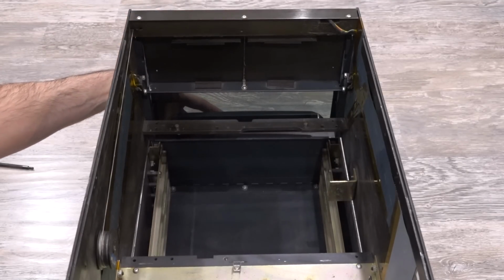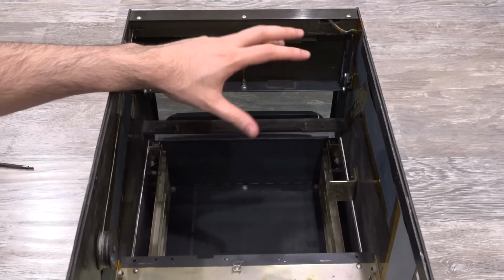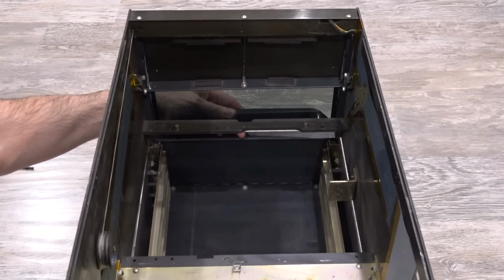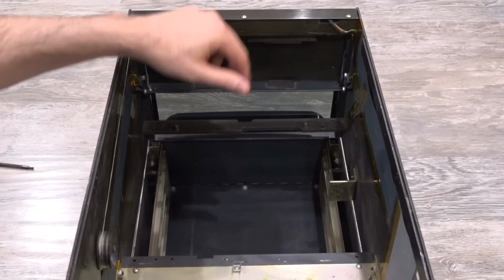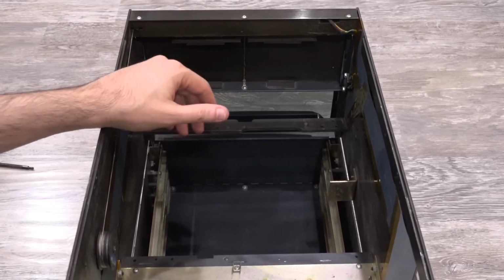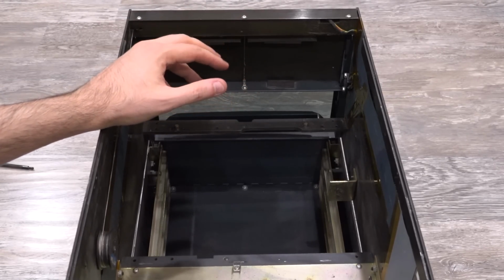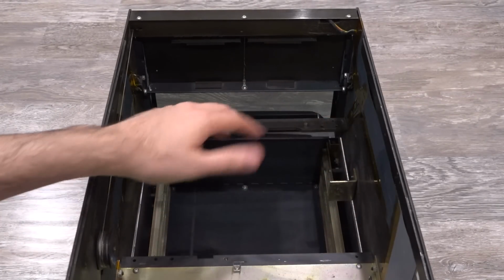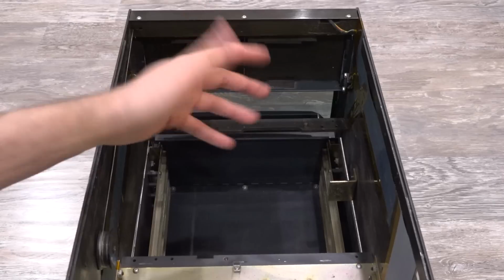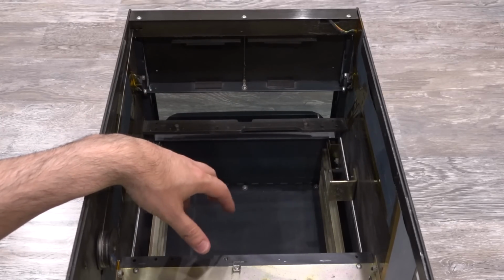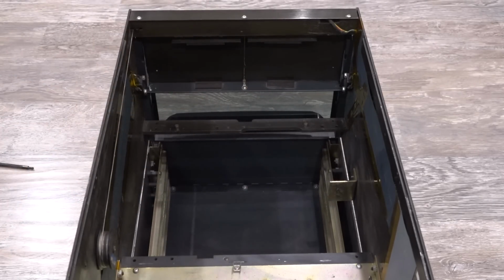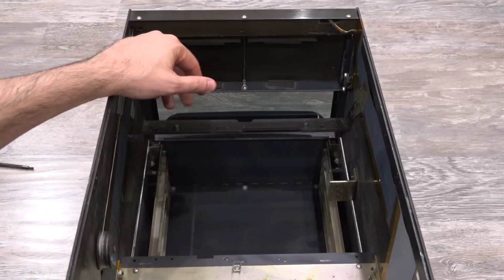So those interlocks mean that they really care about whether this is properly closed or not, because even if you close it a little bit at an angle, only one of the interlocks will be activated. But there's no other interlock that I can find anywhere else. So if the unit is taken apart, for example, or a top is missing or something on the side is missing, you wouldn't know. I mean, there's only so many interlocks you can put into something like this, but they clearly care about that. It's all cleaned up, and I did the best I could.